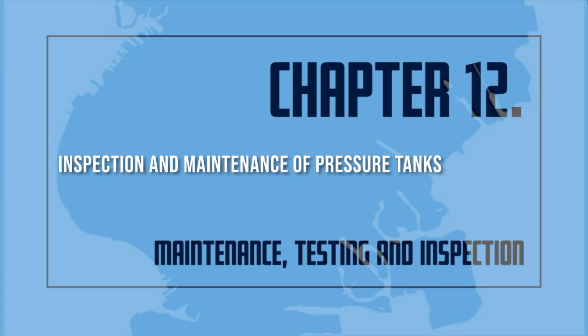After visually inspecting the water gauge valve, the valve should be closed. When the valve is closed, the water and air in the tank are isolated from the sight glass. If the gauge glass breaks, the volume of water and the air pressure will not be affected.